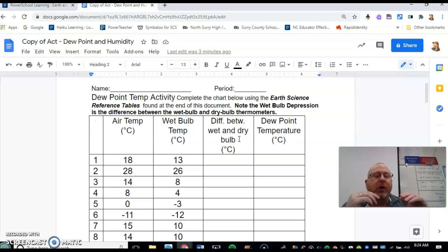And anytime water evaporates, that pulls heat out of something. So what happens is you would get a temperature difference. You'd have a dry thermometer and a wet thermometer. And whatever the temperature difference was, you could calculate the humidity in the atmosphere. And so that's where the term wet bulb and dry bulb come from.